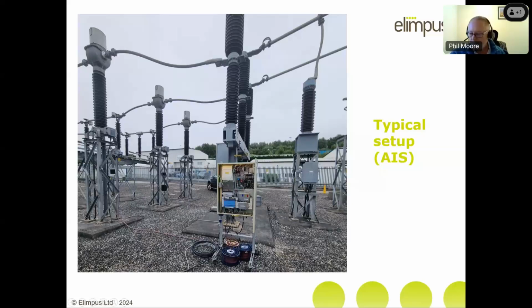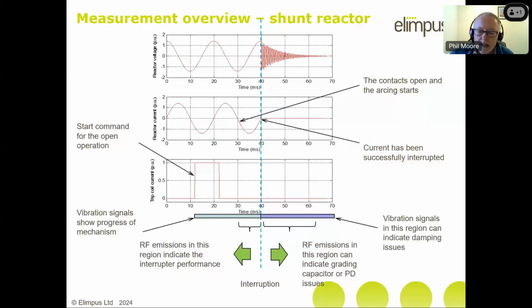So a little overview, probably just to repeat what I said earlier, but to put a little more substance to it. This is an overview of the measurements. Here we have the reactor voltage. You've seen this before. Here's the 50 Hertz, eventually culminating in the device interrupting, and then we go into this high frequency transient, the reactor transient. I'm showing here the line current, whether we measure it or not, where the current goes out at the point of interruption. And then here are the trip signals. The trip signals occur at about 12 milliseconds or so.